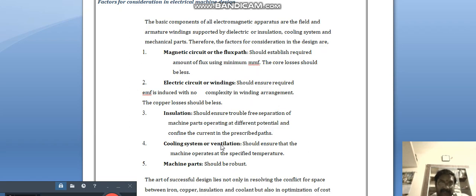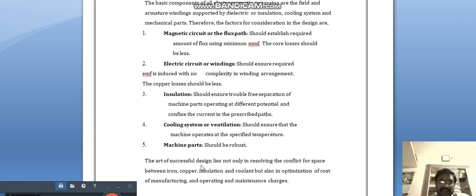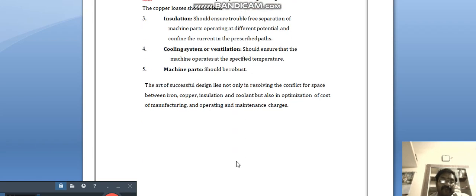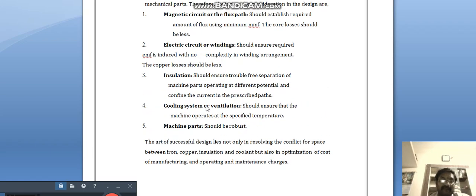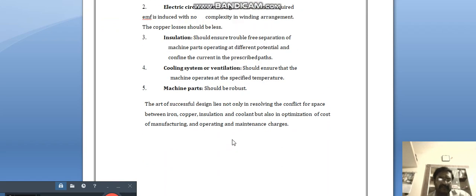Cooling systems and ventilation should ensure that the machine operates at the specified temperature, since increased temperature reduces efficiency. Machine parts should be robust — not weakened — and should withstand the vibrations generated in motors, generators, or transformers. The art of successful design lies not only in resolving the conflict for space between iron, copper, and insulation, but also in the optimization of cost.